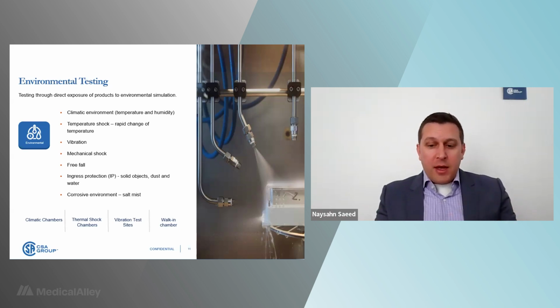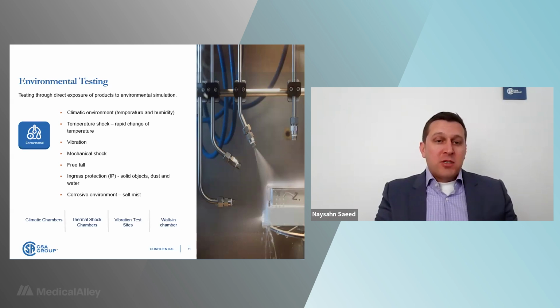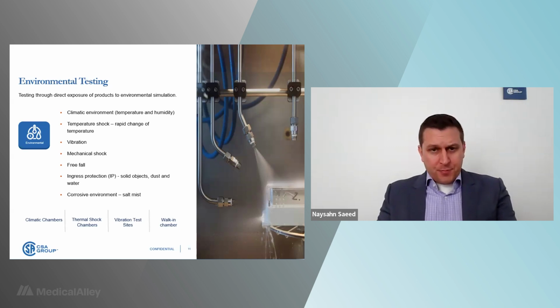Depending on the use environment, as more products are used in more extreme environments or are used in emergency services, whether that's an air ambulance or an ambulance on the ground, there are additional requirements for shock and vibration, for example, for climactic changes, et cetera. And, as we always have, we have the facilities to do that testing. But more than that, we can help you understand what that testing is going to be so you're prepared for it, so that doesn't end up as a failure at the end of the process.